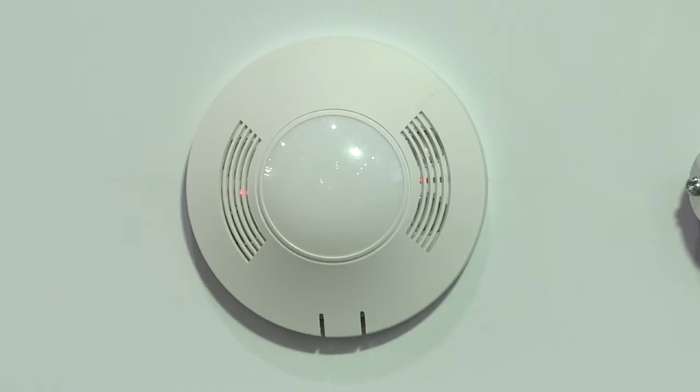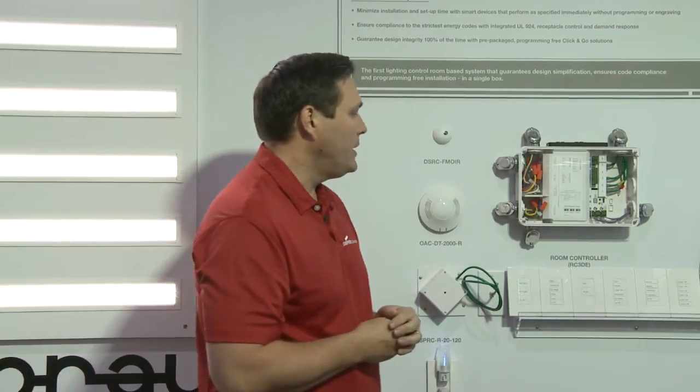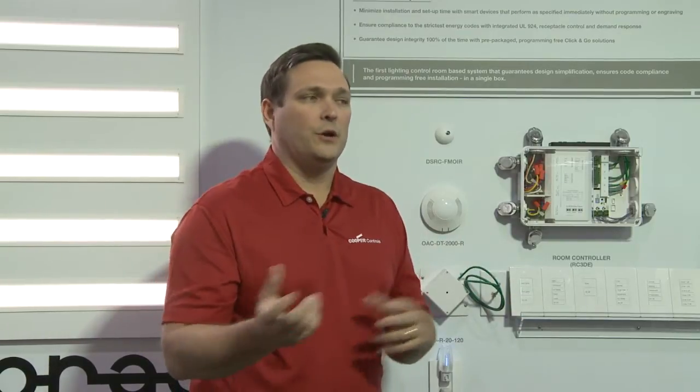Next on our line is our Occupancy Sensor. The RoomController will connect to all occupancy sensors that are part of the GreenGate family. We have something called an Occupancy Sensor Coupler that the GreenGate sensor connects to, making it a quick-connect connection. That allows us to use ceiling sensors in 2,000 square feet, 1,000 square feet, and 500 square feet coverage, dual-tech, passive-infrared, and ultrasonic configurations. We can also easily switch to our wall-corner sensors if there's suspended lighting such as CoreLite or Neoray in the space.